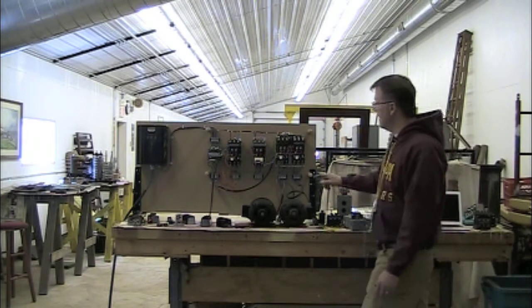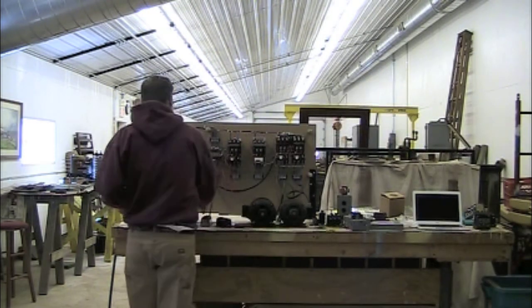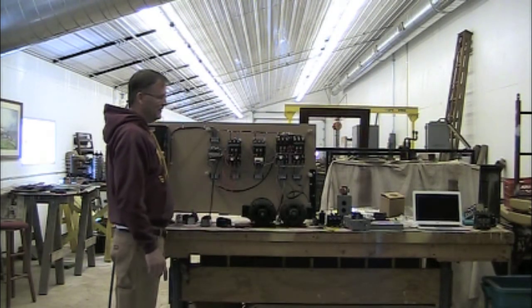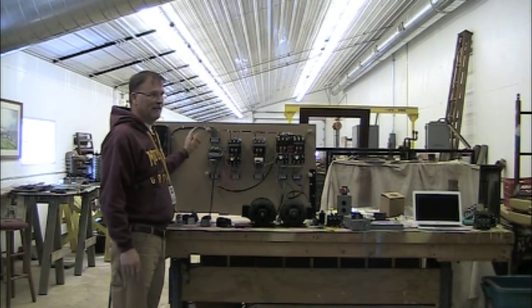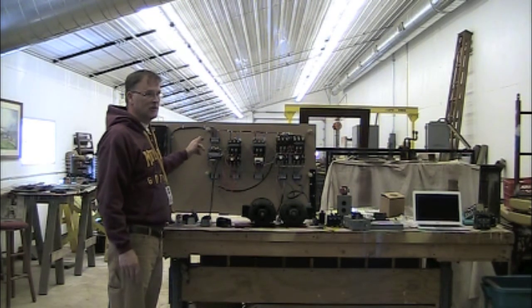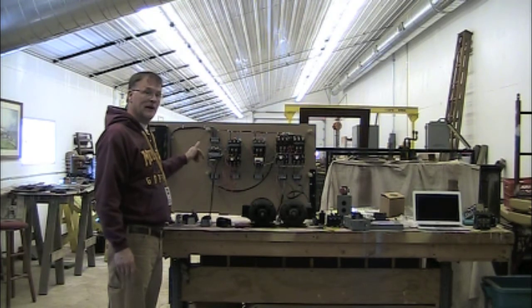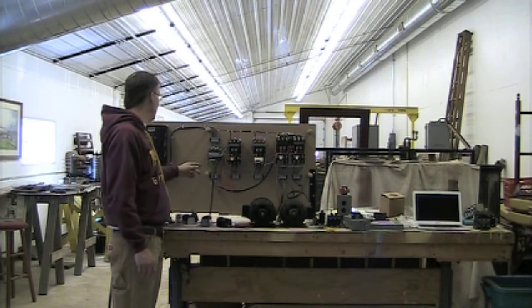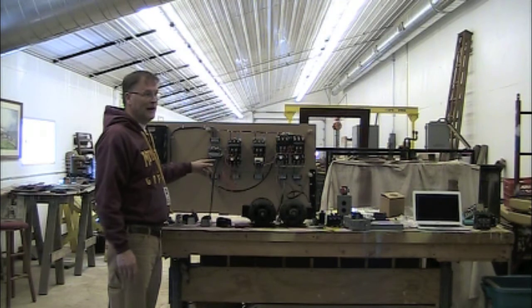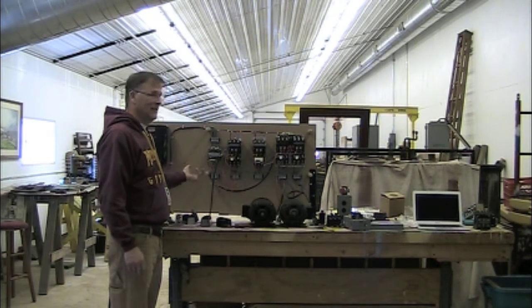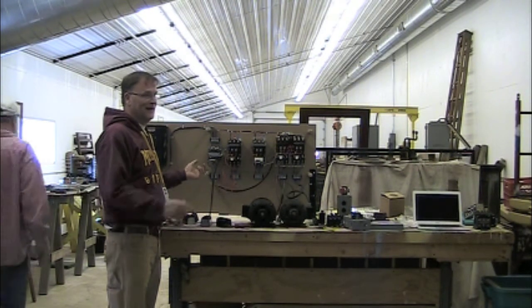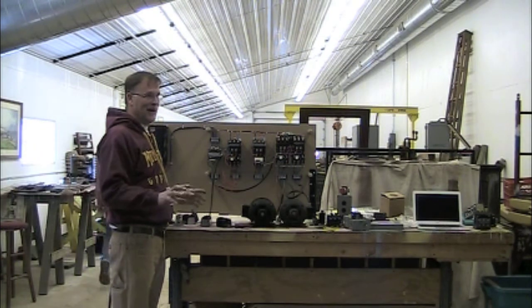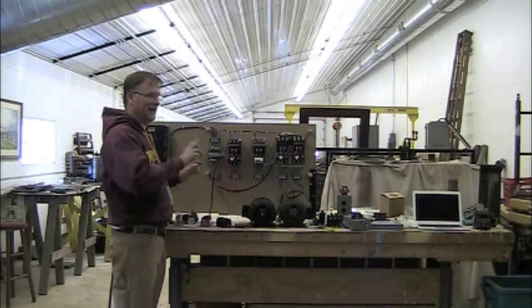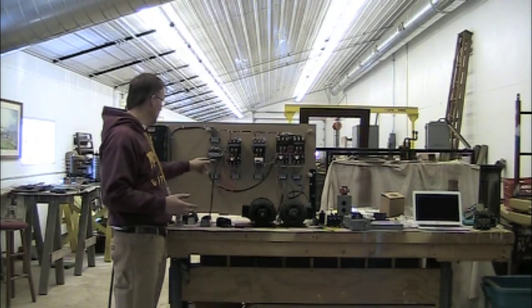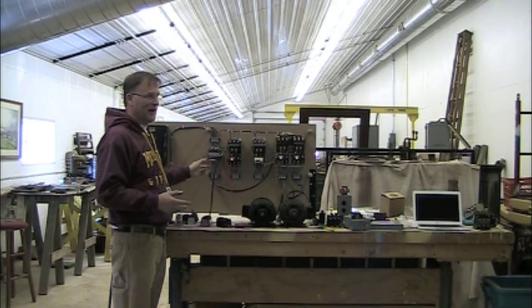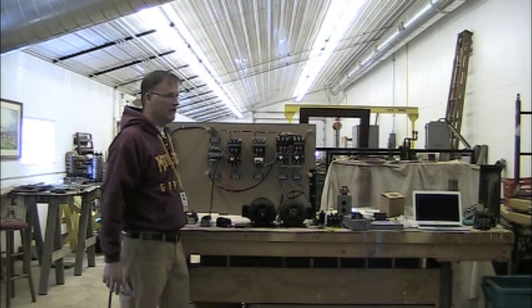The one thing that's missing on here, depending on the size of it and the size of what you're fed with, is that this should actually have fuses, 2 fuses coming in. There should be one on each line coming into the control transformer. That depends on the size. And then there's only one on the output side because it's an isolated circuit. It can only flow through it. It's not bonded to ground or anything, so it can't short from both directions because there's no potential between the secondary winding and anywhere. So there's only one fuse that's needed.